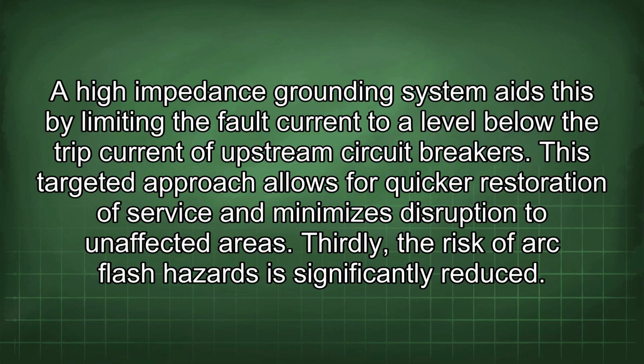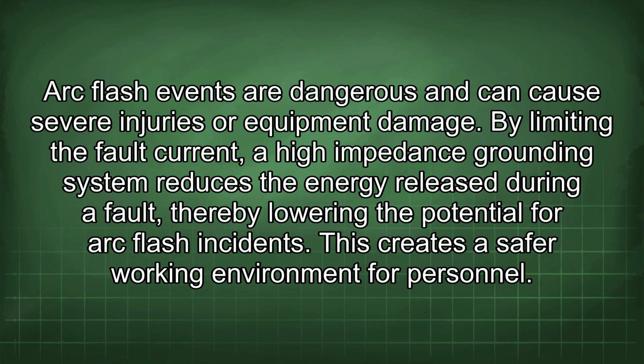Thirdly, the risk of arc flash hazards is significantly reduced. Arc flash events are dangerous and can cause severe injuries or equipment damage. By limiting the fault current, a high impedance grounding system reduces the energy release during a fault, thereby lowering the potential for arc flash incidents. This creates a safer working environment for personnel.